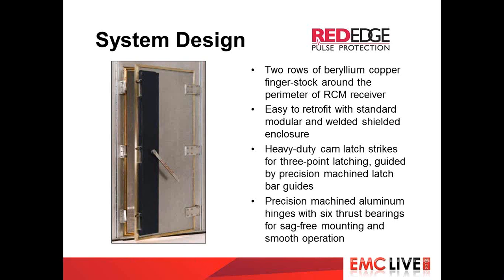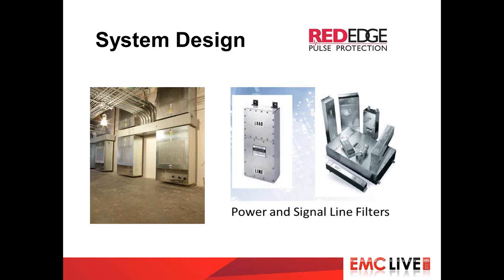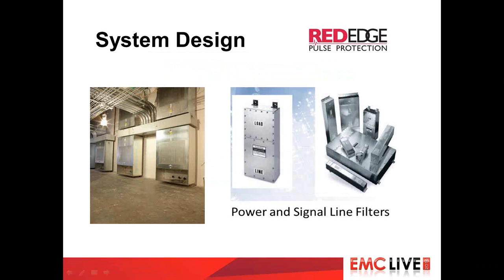What we're looking at in this photograph are power line filters. The photograph to the left is showing a cluster of 4 1200 amp units that are making up power entry to this facility. So that's a 4800 amp power entry component that you're looking at. And power and signal line filters are available. Might add that these types of filters for EMP protection must be inductive input type filters with surge arresting devices on them. Most commonly MOV devices, metal oxide varistors.